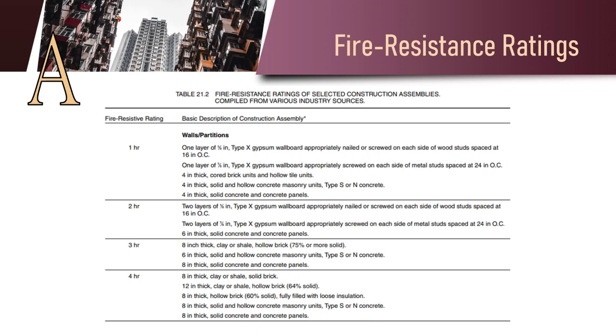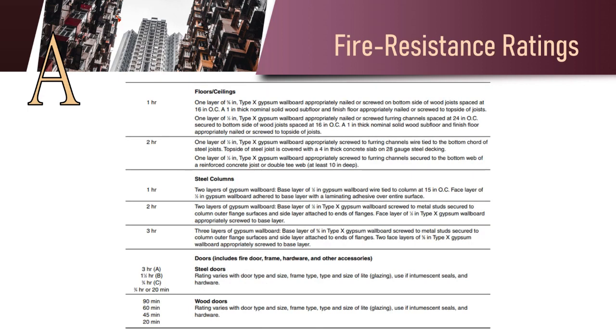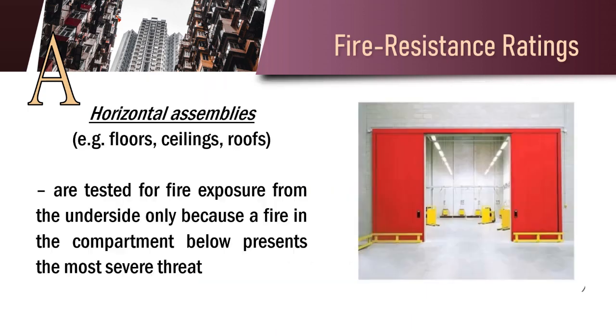For walls and partitions, the rating includes 1 hour, 2 hours, 3 hours and 4 hours depending on the construction assembly. For floors and ceilings, the ratings are 1 hour and 2 hours. For steel columns, the ratings are 1 hour, 2 hours, and 3 hours. For doors, specifically steel doors, the ratings are 3 hours, 1.5 hour, 3/4 hour, and 20 minutes. For wood doors, the ratings are 90 minutes, 60 minutes, 45 minutes, and 20 minutes. Other assemblies, like horizontal assemblies, partitions, and exterior walls, require only part or parts to have a fire resistance rating.